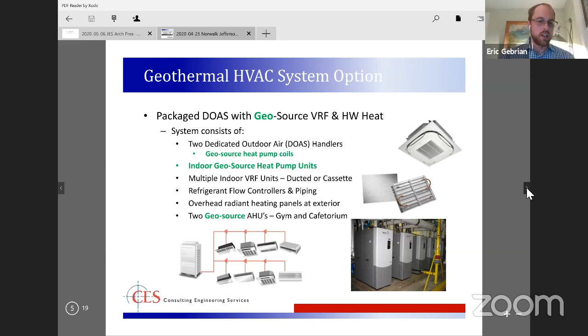So the geothermal option for this school is exactly that: taking the same DOAS ventilation system and the same Mitsubishi or Daikin heat pump cooling and heating system, and adding the geothermal piece to it. We'd still have the same indoor units feeding the classrooms, the same direct ventilation and exhaust air from the classrooms. Outside on the site, instead of having units up on the roof -- bigger versions of the air conditioning unit outside your house -- we'd have a series of wells drilled out in the field that you wouldn't see, since they're underground, interfacing with a different type of system inside the building. That's the major difference. Lisa, go to the next slide and I'll get into that a bit more.